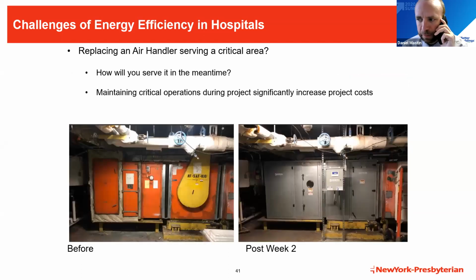Here's another example: we're replacing air handlers in critical areas. When doing this, we need to find another way to supply air to the space. This might mean installing temporary ducting from another air handler to serve the space temporarily, or installing a temporary air handler. We have a project right now where we had to crane lift a 25,000 CFM air handler to the roof temporarily while we replace two air handlers serving an OR. This serves as a swing air handler. At the end of the project, we'll remove the temporary air handler from the roof. Again, it requires two crane picks, significantly increasing the complexity of the project and also the cost.